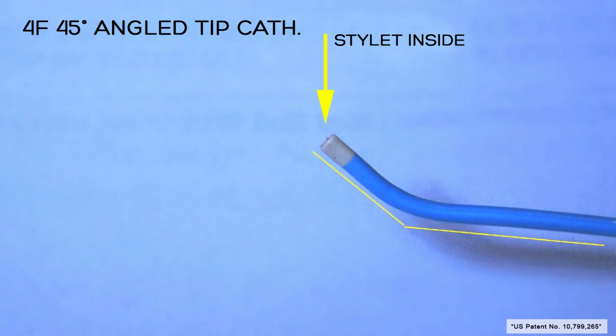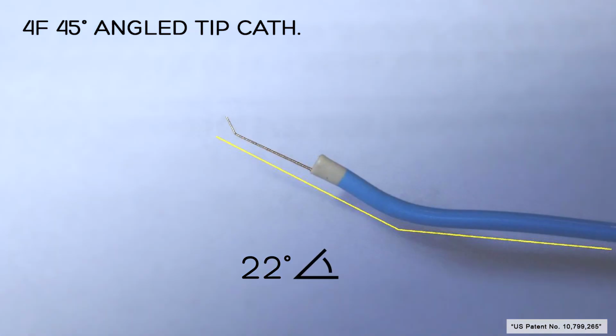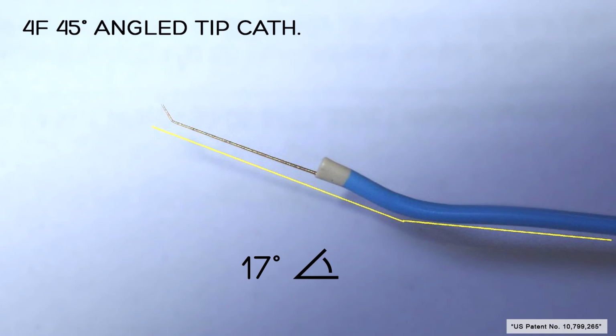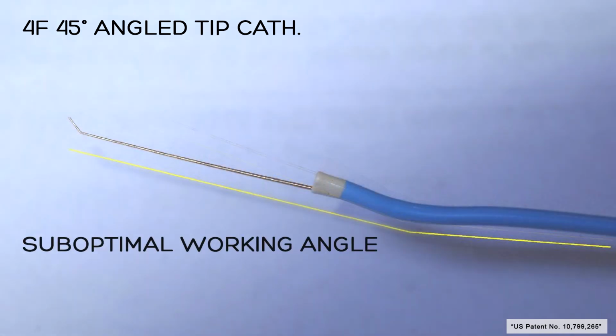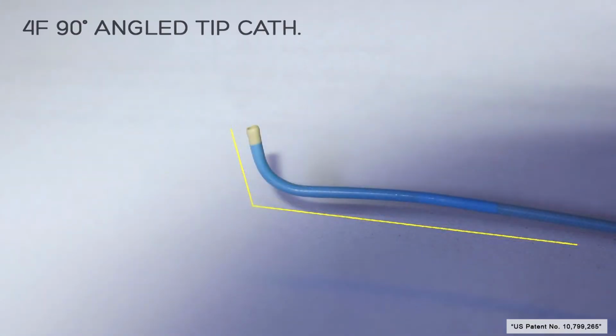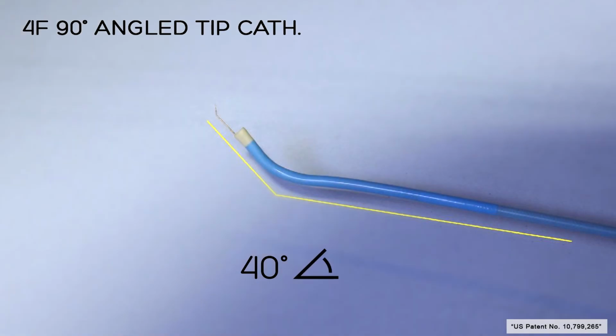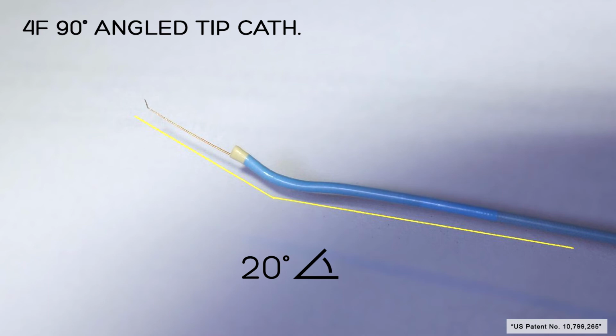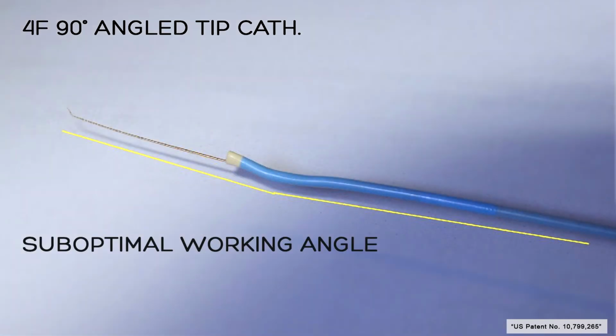The effective operational range of the system, using a 45-degree angled catheter, can vary from 22 to 17 degrees. Further stylet advancement makes the reduced working angle suboptimal. When using a 90 degrees angled catheter, the effective operational range can vary from 35 to 20 degrees. Even in this case, further advancement of the stylet leads to a suboptimal working angle.